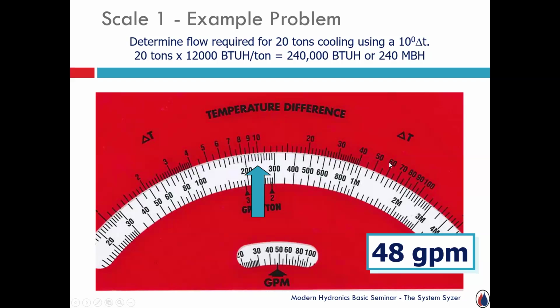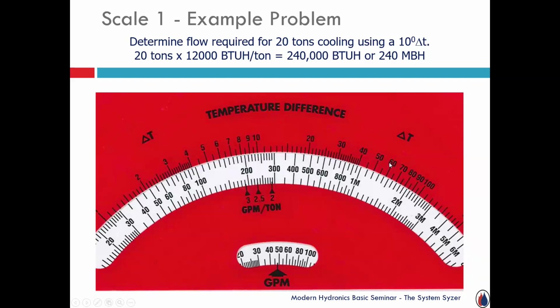One of the things just to point out on the wheel, let me just move backwards for a second. On that scale, down at the bottom part of that white band, you'll see GPM per ton. So he actually highlighted 3 pretty common accepted temperature rises in chilled water. And if you line them up, it's pretty close to straight across an 8-degree rise, a 10-degree rise, and a 12-degree rise. So within the chilled water world, those are pretty standard. You can design them on 8, 10, or 12. We just picked 10. 10 seems to be pretty standard, but it can move a little bit. But they just highlighted on the scale, if you're working with chilled water, what's your temperature rise? And then you can figure out 3 gallons, 2.5, or 2 gallons a minute per ton.